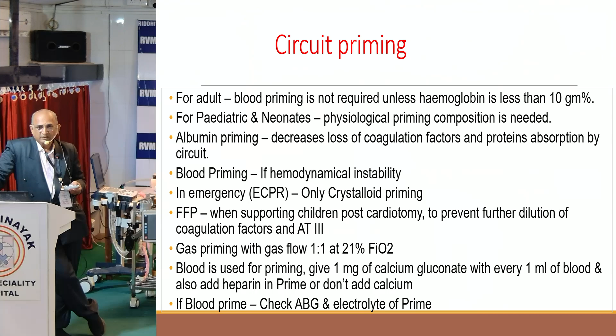Okay. Now see, first you have to always de-air the pump. And this de-airing of the pump will be gravity guided. So you have to keep this in this position so that there is no air. Air always moves up, so air is replaced by the crystalloids. And then you have to turn it like this, so all the air goes up and gets replaced by the crystalloids. Then it will go here in the oxygenator. You have to open the oxygenator pigtails here so that air comes out and it gets filled up.